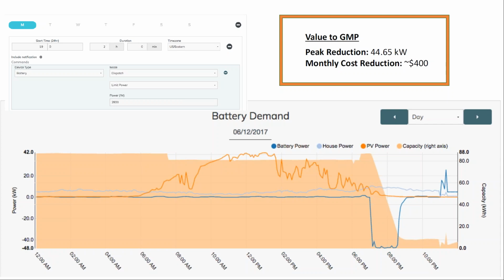So you can see the dark blue line is the battery power. It hovers around 0 for most of the day, meaning it's just sitting there idling, waiting for an outage or an event. At 7 o'clock it spikes down, an aggregate demand reduction of all the units, dropping to about negative 45 kW, staying there for a 2-hour duration, then hopping back up to 0 around 9 o'clock. For that 2-hour window we're reducing our overall peak by 45 kW, and only one of those hours actually counts as our peak, but we've effectively done exactly what we hoped.